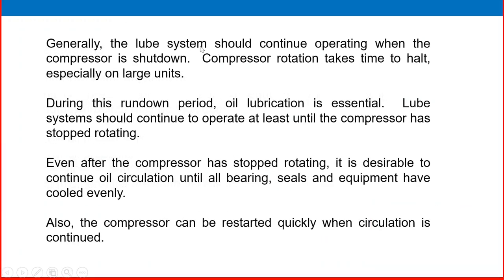The lube oil system should continue operating when the compressor is shut down, because compressor rotation takes time to halt — especially on large units. During this run-down period, lubrication is essential. The lube system should continue to operate at least until the compressor has stopped rotating, and ideally until all bearings, seals, and equipment have cooled evenly. Continuing circulation also allows quicker restart.